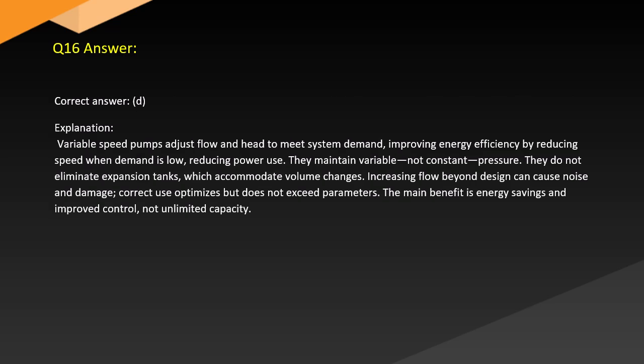Answer. Correct answer, D. Explanation. Variable speed pumps adjust flow and head to meet system demand, improving energy efficiency by reducing speed when demand is low, reducing power use. They maintain variable, not constant, pressure. They do not eliminate expansion tanks, which accommodate volume changes. Increasing flow beyond design can cause noise and damage. The correct use optimizes but does not exceed parameters. The main benefit is energy savings and improved control, not unlimited capacity.